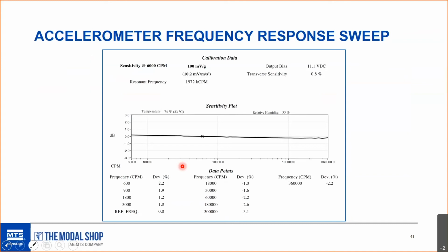And you can see in the data at the bottom there, the low end frequency is 600 cycles per minute, and the high end is 360,000. And the maximum deviation that we saw from 100 millivolts per G was 3.1% down.